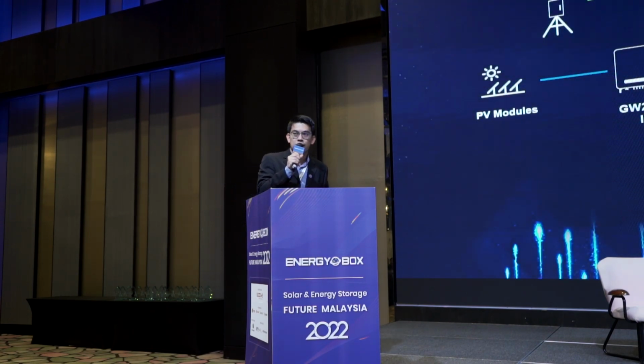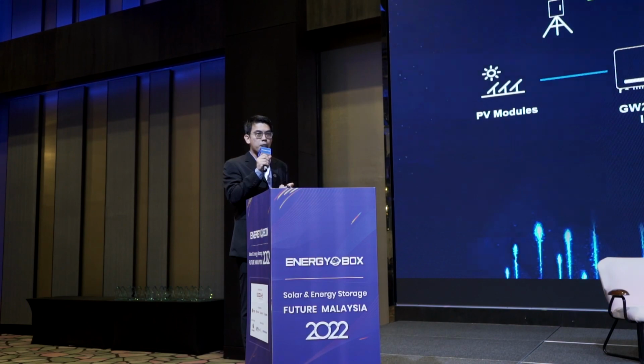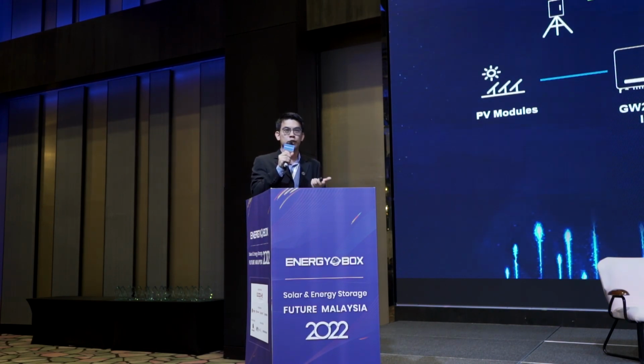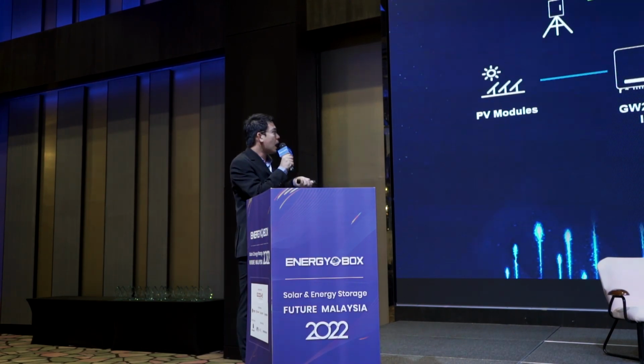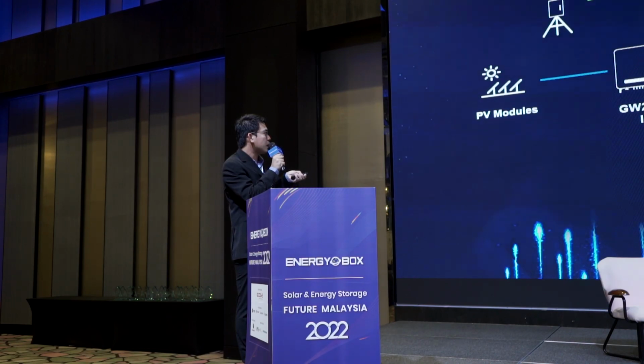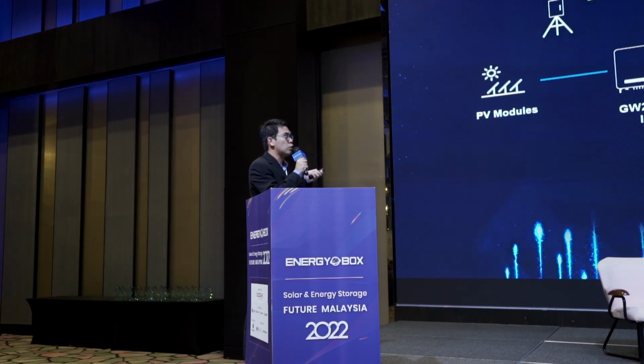The next one would be the utility scale turnkey solutions. I'm proud to announce that GoodWe has already secured 2 LSS Mentari projects in Malaysia. I think that is a great milestone and a good achievement for us. We are able to provide the whole turnkey solution, from the 250 kilowatt string inverters, as well as the MV station for 35 kV as well as 11 kV. It is a 6.75 MVA MV station, as well as the whole solution on the monitoring.